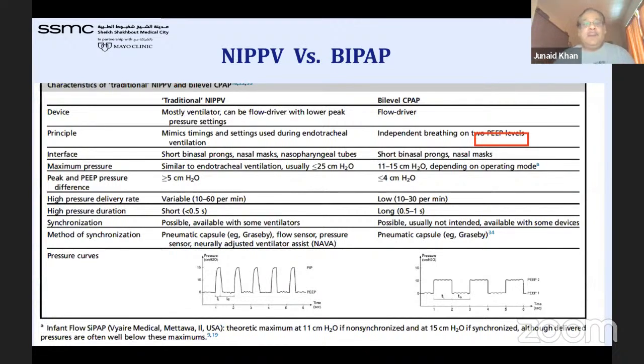So what is the BiPAP, and what is the NIPPV, and what is the difference? Traditionally, for the NIPPV it's mostly the ventilator, but it can be a flow driver. For the BiPAP level, you can buy the flow driver, or some machines are doing this. The principle is to mimic the timings and settings used during endotracheal ventilation. So the NIPPV is the same as, or mimics, invasive ventilation. Here, with independent breathing on 2 PEEP levels, that's the main difference.